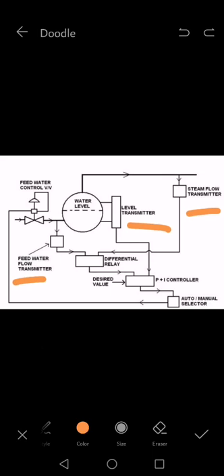In the same way, if the steam demand decreases, your water level will increase in the drum. So simultaneously, a signal will go from the P+I controller to the feed water control valve and the valve will close a little since the water level is high.